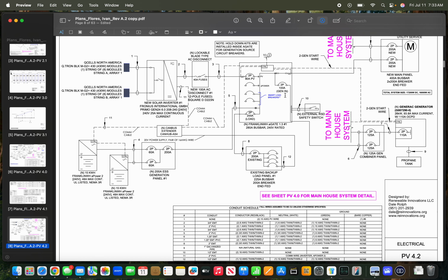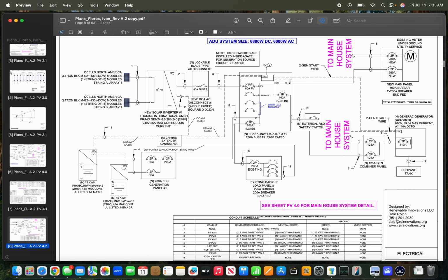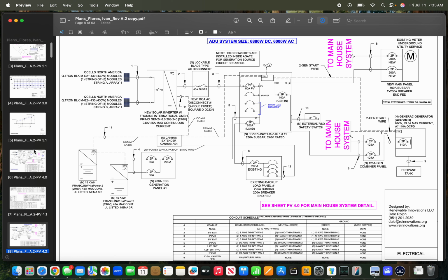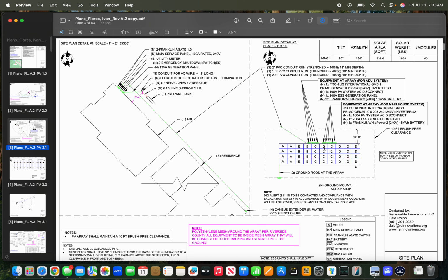Now this site is a little bit smaller. We only have 2 batteries on it, but again, we designed it for expansion. So you can see we still have a 200 amp sub panel with a 200 amp breaker. There's going to be plenty of spaces available in here for expansion on this particular site. You can actually do up to, I believe, 15 batteries with the Franklin equipment if this homeowner wanted to do that. And that's kind of why I designed it going from the center out.